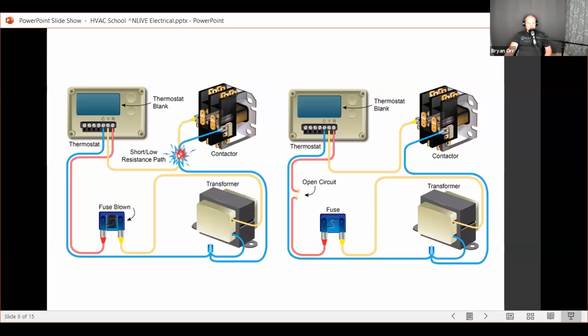So a short is an undesigned path, generally a low resistance path that results in an overcurrent condition that blows a fuse, trips a breaker, something like that. An open circuit is a break in the path of some sort, so an undesigned break that results in things not happening that should be happening.